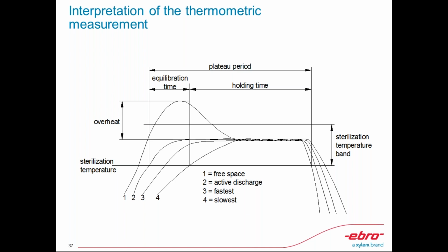Because why? Number one, the air evacuation. You don't know how important it is for the CSSD operators to know that everything inside the autoclave is 100% saturated steam. This to them is very important because it will be affecting the heat penetration capabilities of the autoclave and the process. Oh my God, I have 5 minutes left.